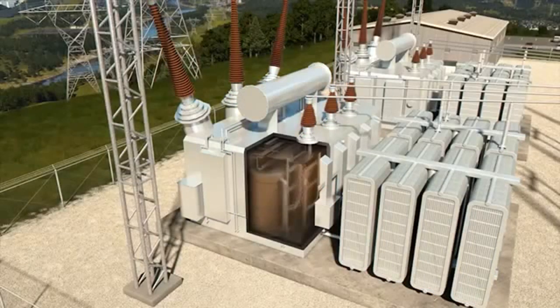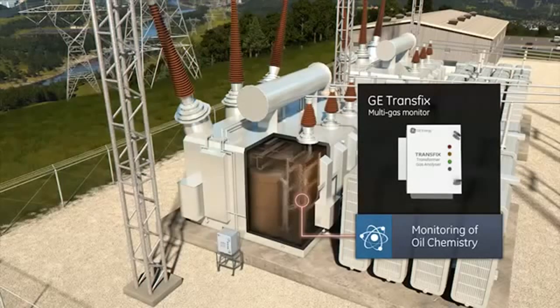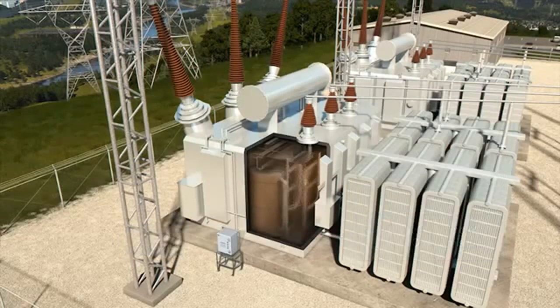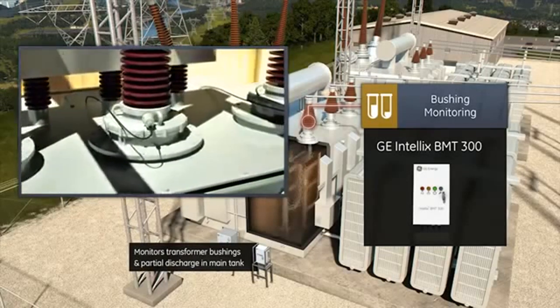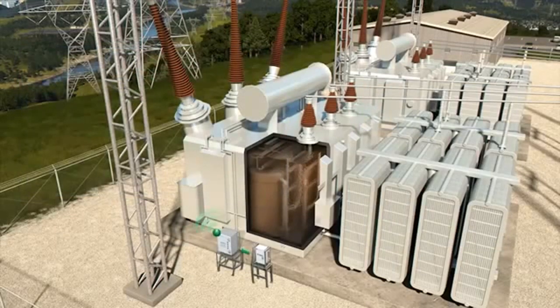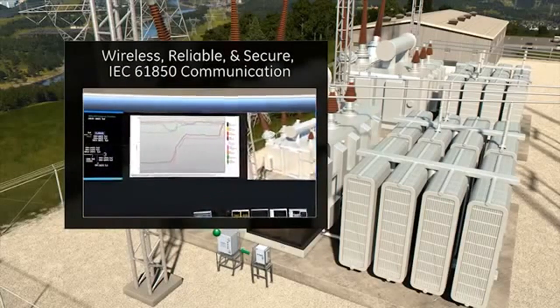Continuous monitoring of oil chemistry can provide advanced knowledge of developing fault conditions. GE's Transfix Multigas Monitor is regularly testing trace amounts of the gases in this transformer's oil using photoacoustic spectroscopy. GE's Intellix BMT-300 is continuously monitoring the condition of the transformer bushings and partial discharge activity within the main tank. The results are communicated to the control center via IEC 61850 communications over a reliable and secure GE wireless network.